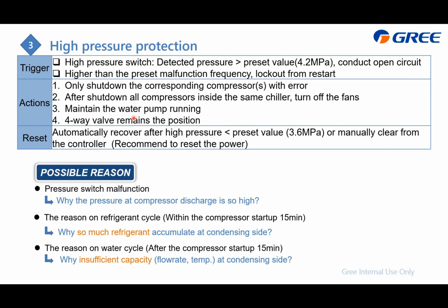And then the water pump and the four-way valve are handled the same as for the other errors. And of course, this can automatically recover if the detected pressure is less than this value, 3.6 megapascal. Or you can manually clear it from the controller. And of course, we recommend resetting the power for this issue. So, the possible reasons I divided into these three, which is whether the detected pressure is really so high or not.